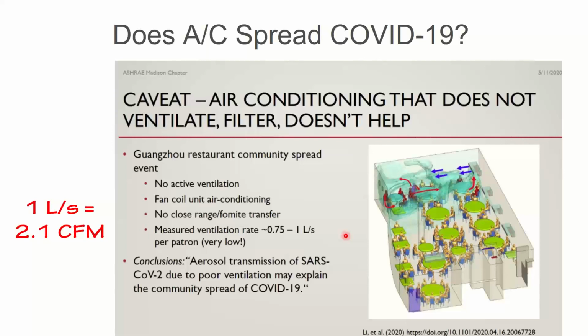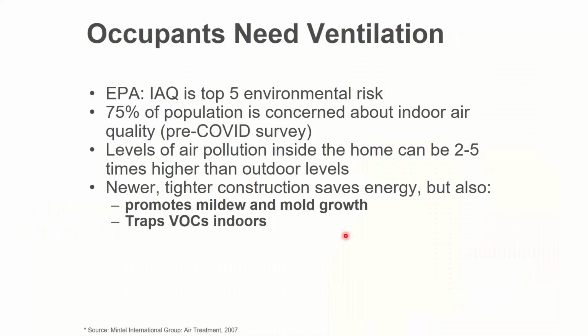And you're probably going to need 10 CFM. Well, a restaurant probably needs 7.5 CFM per person, and I think it's 0.06 CFM per square foot, and you add them together, right? Either case, 2 is extremely low. So they basically have no ventilation air. That's the real crux of the problem, not just the fact that they have an air conditioner.